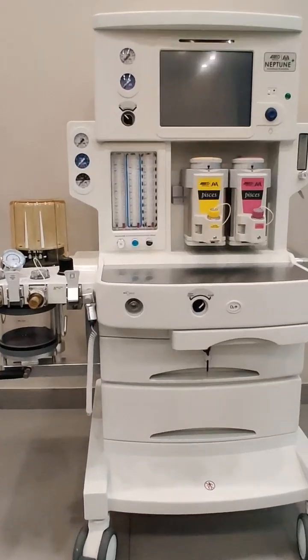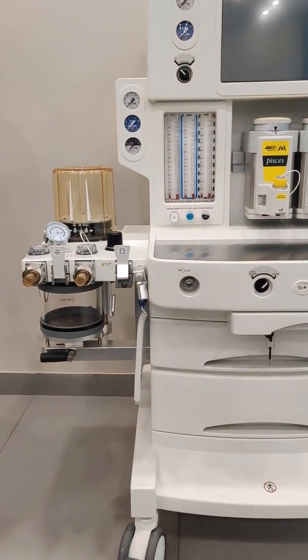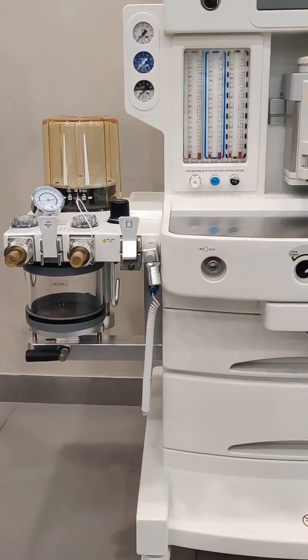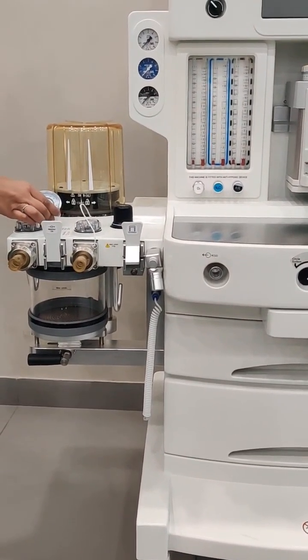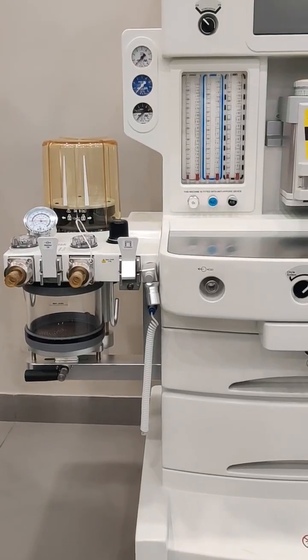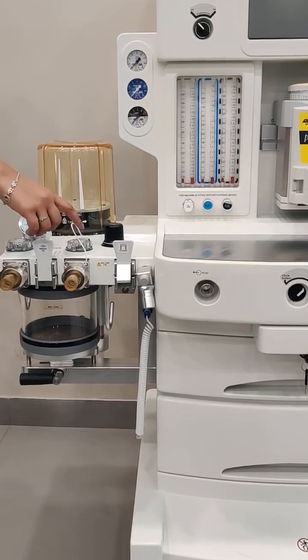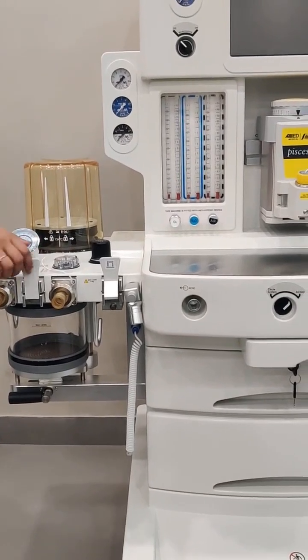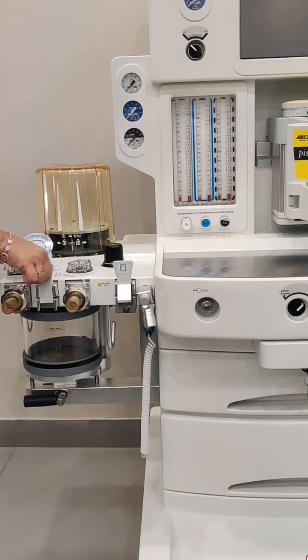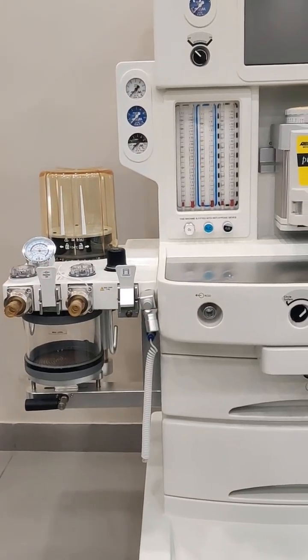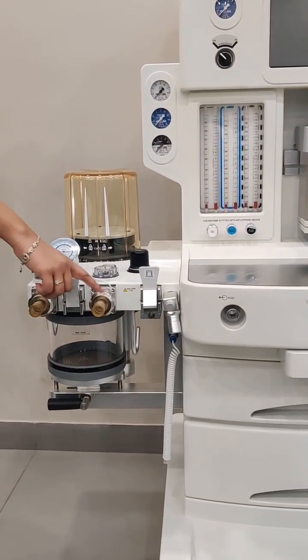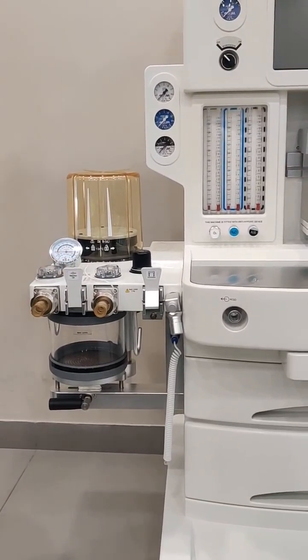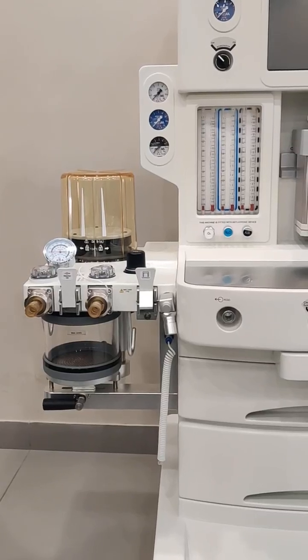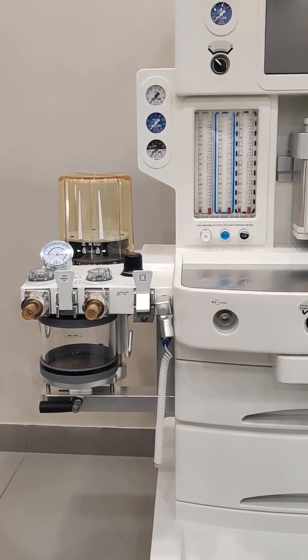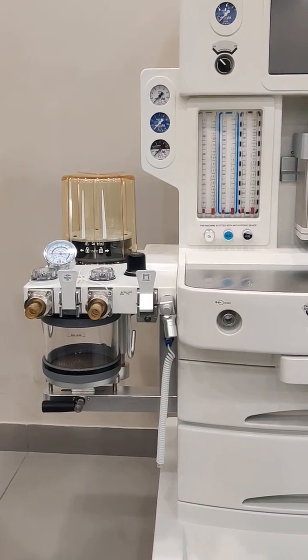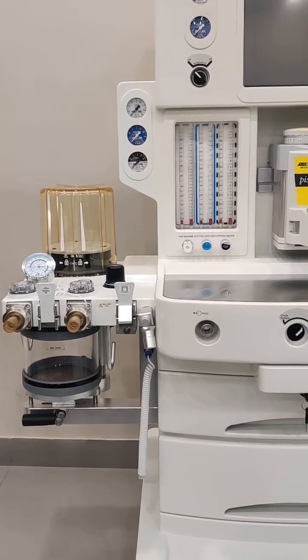Then the machine is equipped with the circle absorber system. We are giving a single canister circle absorber system, and we have the airway pressure manometer. We have the bag to vent switch for automatic and manual ventilation. Then we have the circle absorber bypass switch. Then the inspiratory port and expiratory port come with an integrated flow sensor. So we have a dedicated flow sensor each for the inspiratory parameters as well as for the expiratory parameters. Then for connecting the breathing bag, we have a connector over here.